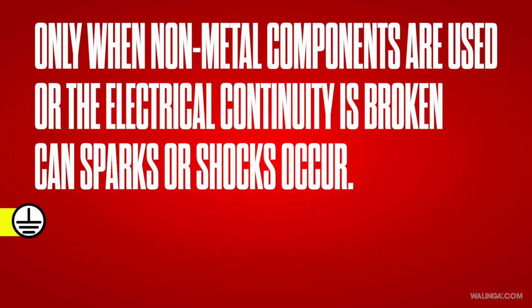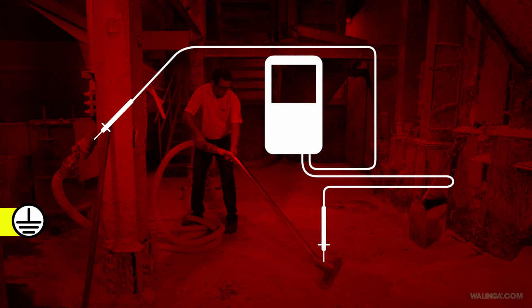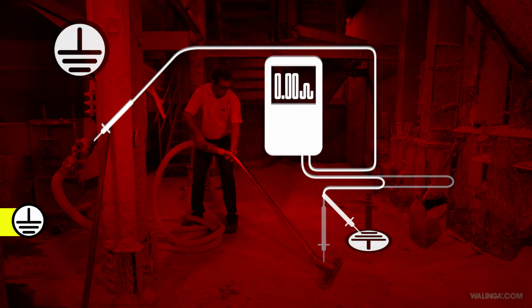Only when non-metal components are used or the electrical continuity is broken can sparks or shocks occur. Using an ohmmeter, check the electrical continuity of the system on a weekly basis as a maintenance item, or if anyone feels a shock.